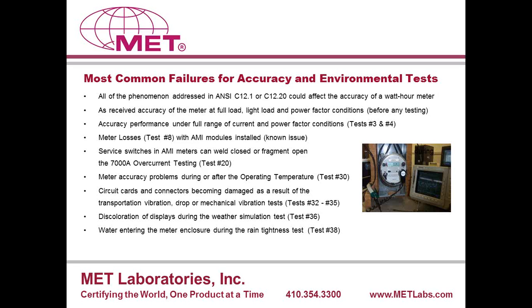Test 32 through 35, the mechanical test, the vibration, the transportation vibration. Most of the time, the meter will operate properly before and after these tests, but we do see quite a bit of, as a result of packaging in particular with the transportation vibration and the drop, where we'll have mechanical damage, a cracked tab or a dome or something of that sort could be an issue.